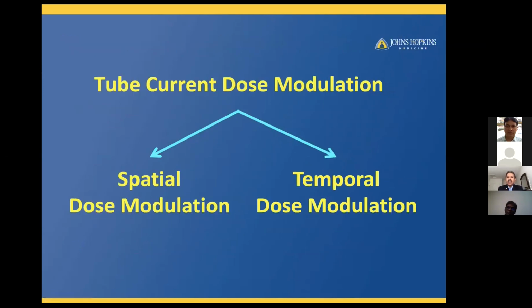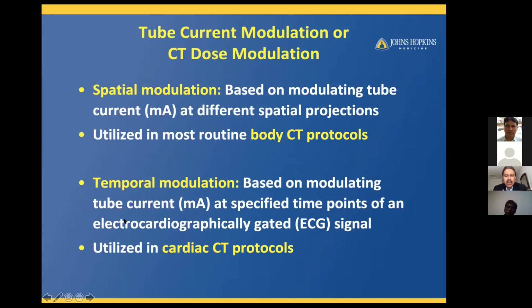And when you talk about dose modulation, there are two types. One is called spatial dose modulation. The other one is called temporal dose modulation. I'm not going to talk much about temporal dose modulation, which is focused towards cardiac CT. But in general, 90% of the time when we say dose modulation, it implies spatial dose modulation. What is spatial dose modulation? It is modulating or changing the tube current based on the patient thickness at different spatial projections. And this is utilized in most body protocols. The temporal modulation is based on modulating tube current at specified time points of an ECG signal, and I'm not going to discuss much about it.